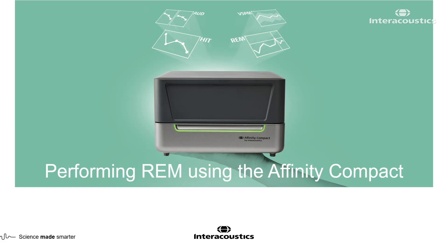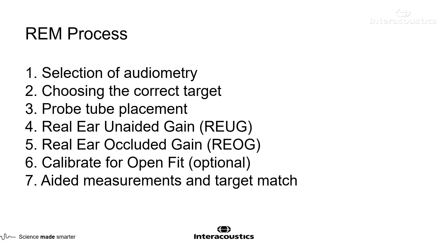This video explains the process required when fitting hearing aids on a patient's ear using an Affinity Compact. The on-ear fitting process involves several steps in this order: first, selection of audiometry; second, choosing the correct target; third, probe tube placement; then the real ear unaided gain; then real ear occluded gain; an optional step of calibrate for open fit; and finally, your aided measurements and target match. All of these steps will be explained further in this video.